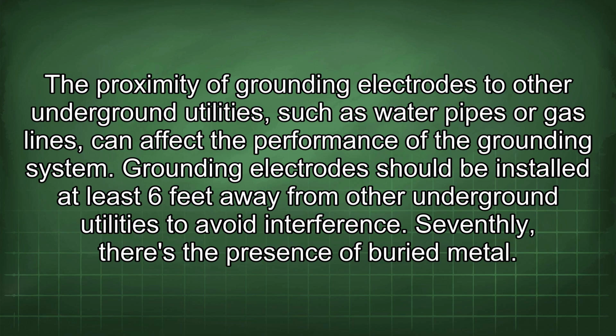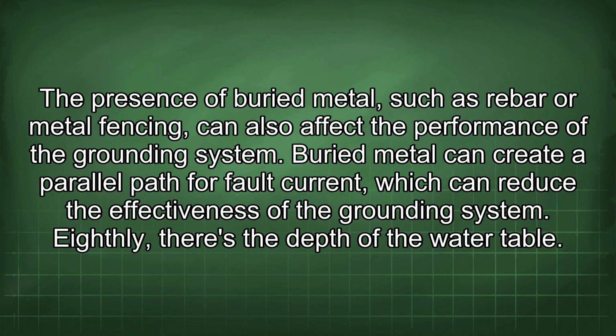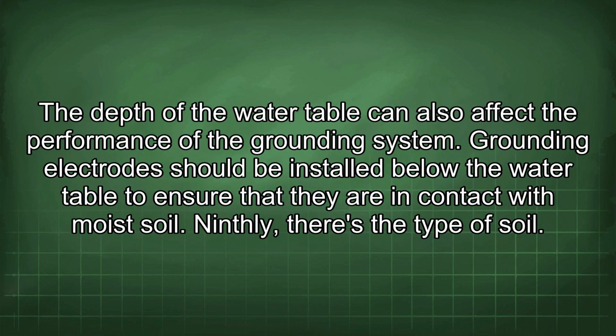Seventhly, there's the presence of buried metal. The presence of buried metal, such as rebar or metal fencing, can also affect the performance of the grounding system. Buried metal can create a parallel path for fault current, which can reduce the effectiveness of the grounding system. Eighthly, there's the depth of the water table. The depth of the water table can also affect the performance of the grounding system. Grounding electrodes should be installed below the water table to ensure that they are in contact with moist soil.